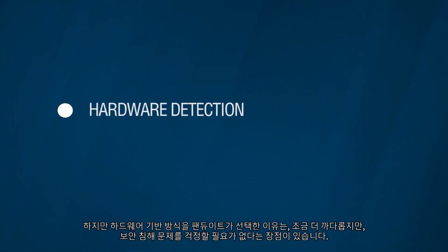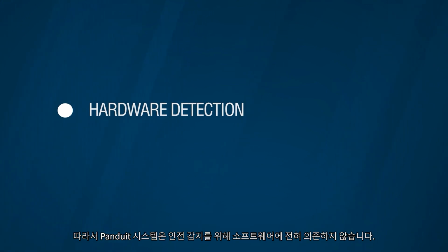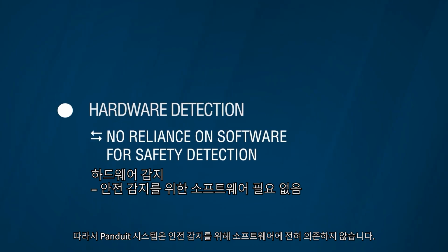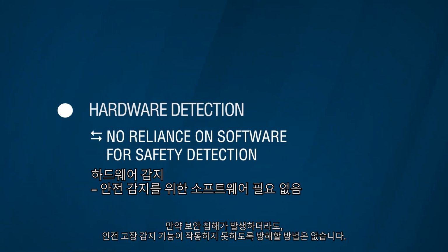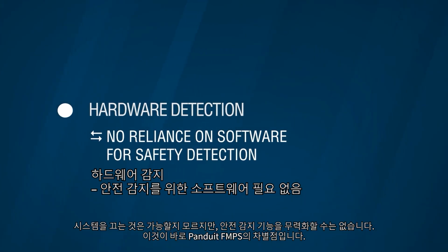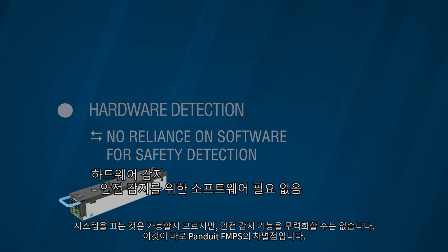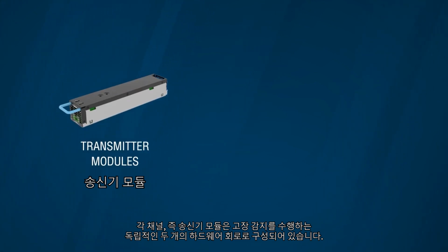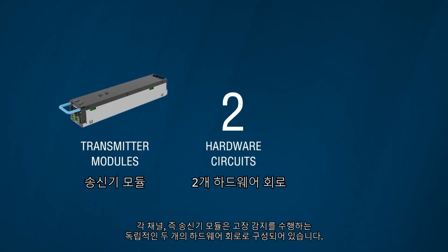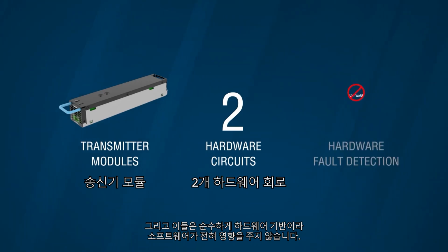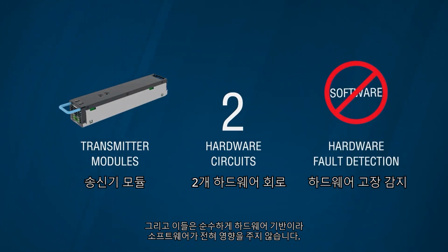Now, if you go the hardware route, which is what Panduit did, it's the harder route to go, but it does save us from having to worry about any security breaches. The Panduit system does not rely on software at all for the safety detection. If there is a security breach, there is no way that they can trip the detection of safety faults. They can maybe turn the system off, but they're not going to be able to disarm the safety detection feature. That goes back to the differentiation. Each of our channels, we call them transmitter modules, has two independent hardware circuits that do our fault detection, and they are purely hardware. There's no software affecting that at all.